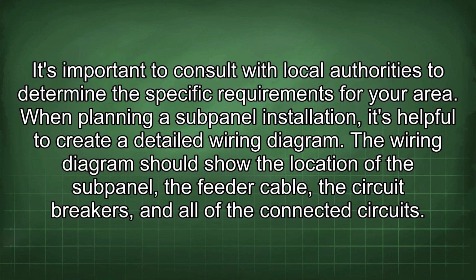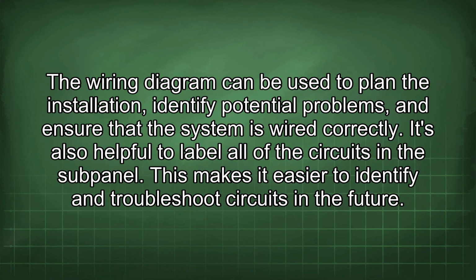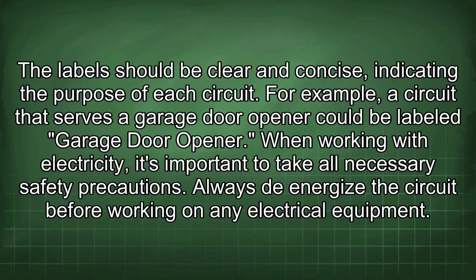When planning a subpanel installation, it's helpful to create a detailed wiring diagram. The wiring diagram should show the location of the subpanel, the feeder cable, the circuit breakers, and all of the connected circuits. The wiring diagram can be used to plan the installation, identify potential problems, and ensure that the system is wired correctly. It's also helpful to label all of the circuits in the subpanel. This makes it easier to identify and troubleshoot circuits in the future. The label should be clear and concise, indicating the purpose of each circuit.